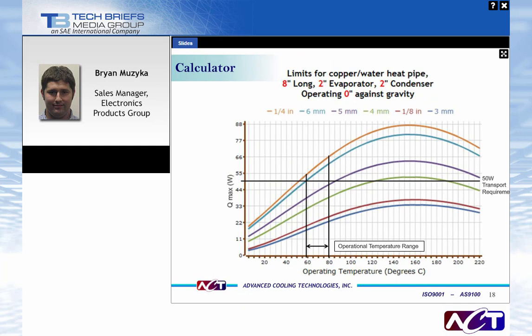This is a screenshot of what our calculator will output. The inputs shown in red are length, evaporator length, condenser length, and orientation — meaning how much of the length operates against gravity. It outputs a curve of various diameter heat pipes and their capillary limits. If you know your operating temperature limit — in this case between 60 and 80 degrees — you can see what size heat pipes you'd need for various powers. For a 50-watt transport requirement, you'd size above that curve, maybe a 6-millimeter or quarter-inch heat pipe.